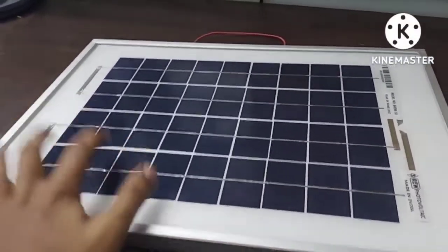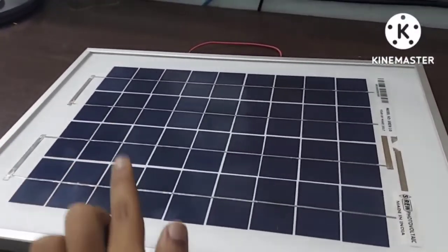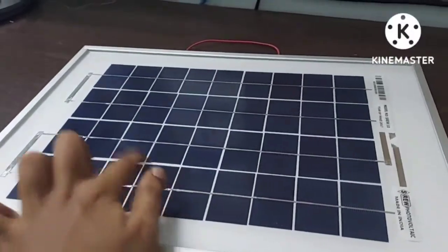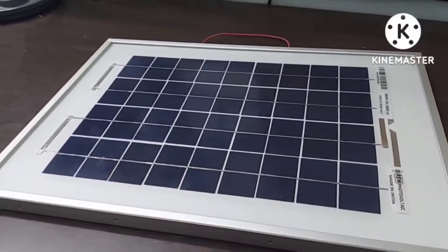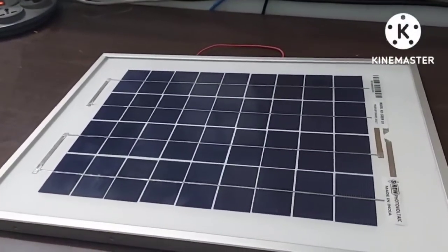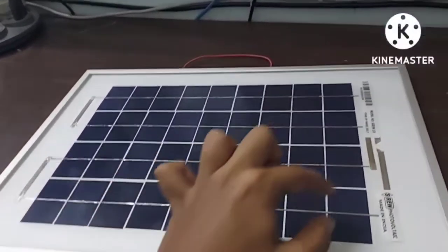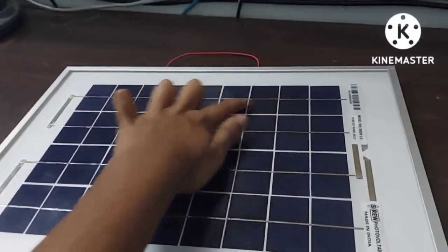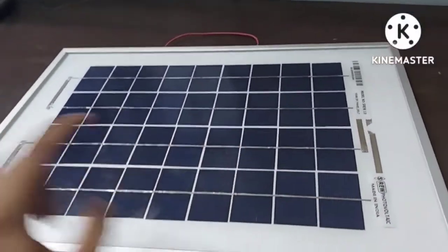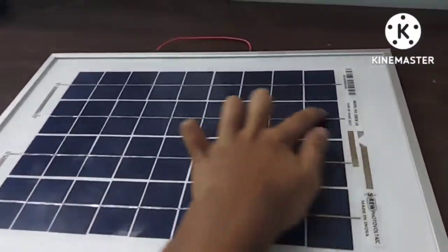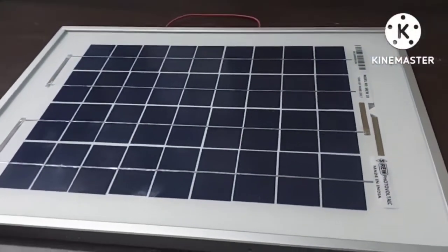When we put panels in series, we are able to increase the voltage, but the current of the entire array is the same as the current of one single panel. Similarly, when we add panels in parallel, we are able to increase the current delivery, but the voltage is the same as the voltage of one panel. Voltage of one panel is basically the voltage of one cell multiplied by the number of cells. Current of one panel is generally the current delivered by one cell. 95% of the solar panels use cells in series. Very few solar panels incorporate cells in parallel on a single panel itself.